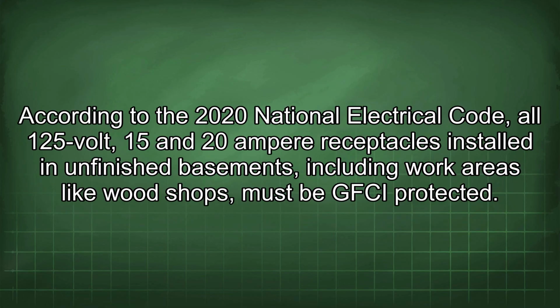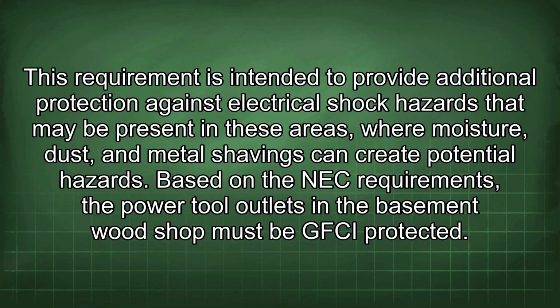According to the 2020 National Electrical Code, all 125-volt, 15 and 20 ampere receptacles installed in unfinished basements, including work areas like wood shops, must be GFCI protected. This requirement is intended to provide additional protection against electrical shock hazards that may be present in these areas, where moisture, dust, and metal shavings can create potential hazards. Based on the NEC requirements, the power tool outlets in the basement wood shop must be GFCI protected.